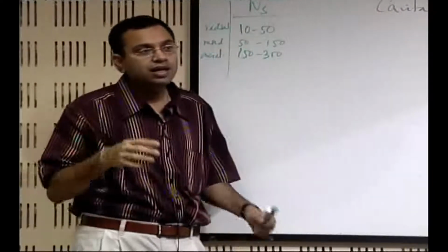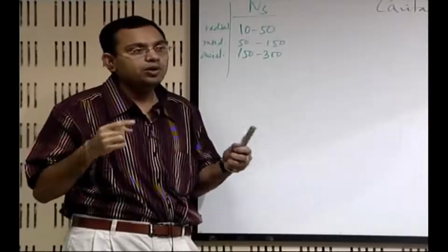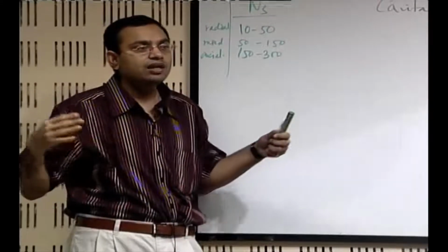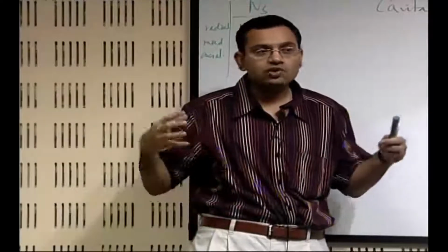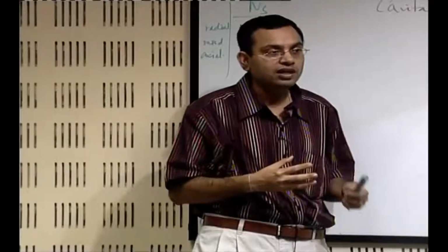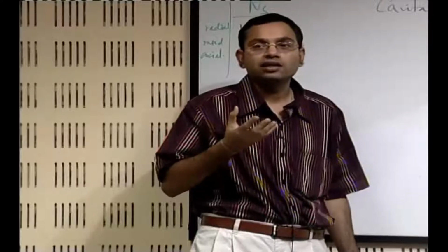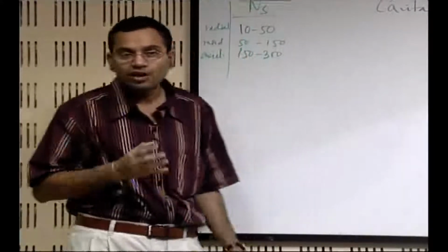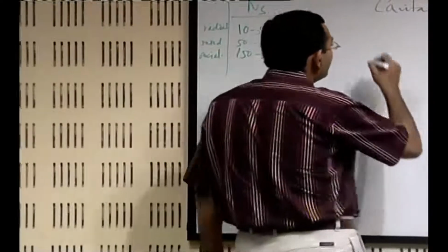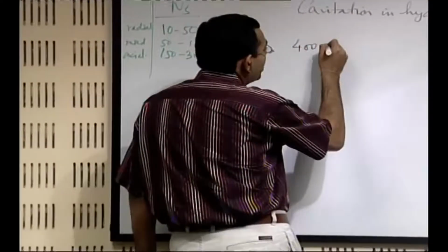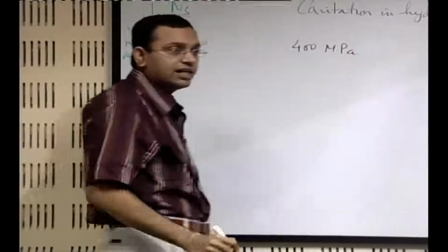Then what will happen? Liquid molecules from all sides will try to rush into that space to fill up that void, and because of strong collision between those molecules, there will be an extremely large increase of pressure. That increase of pressure in a typical hydraulic machine, if it is not designed properly, may be of the order of 400 megapascal, it may be as high as that.